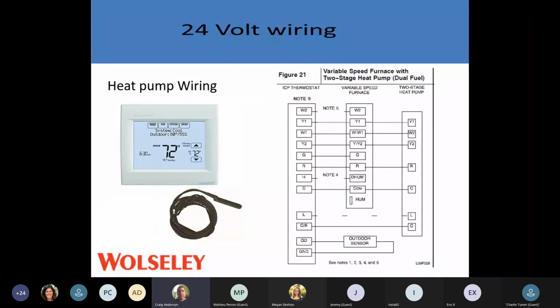So, heat pump wiring. Now the heat pump is switching over into cooling mode, so be mindful of what you're going to be testing outside. Most reversing valves are energized in the cooling mode, so be mindful that you're going to have 24 volts on your O now. We want to energize that reversing valve. We want to change the flow of the Freon going through that heat pump.